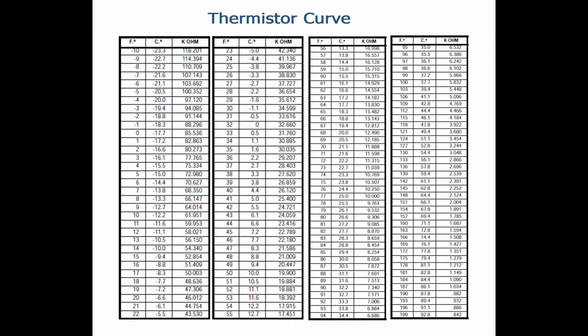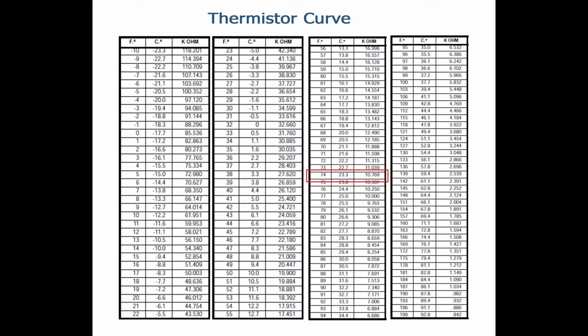The 10.77K ohms that we measured corresponds to a temperature on the thermistor curve chart you see here. As you can see, the reading I got corresponds to 73 degrees or 74 degrees on the thermistor curve chart. Since the machine is sitting in my office at room temperature and I know the room temperature is about 73 degrees, we know that this probe is reading correctly.